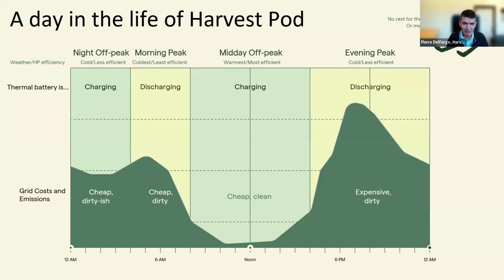Now, in some cases, we run out of storage and then we'll run the heat pump. The occupant comfort and thermal needs are first priority, and load shifting is always second priority, right? So the heat pump will run on peak if needed, but most of the time it won't need to because thermal storage will take all or most of the load.